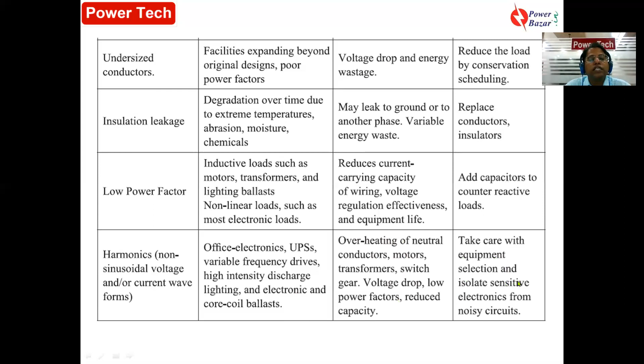Harmonics. What are the reasons? UPS, office electronics, computers, LED, electronic ballast. Now, this results in overheating of neutral conductor, motor, transformer, nuisance tripping, voltage drop, low power factor. These harmonics create a lot of problems. What you have to do? You have to take care of equipment selection, isolate sensitive electronics from noisy circuits, or go for filters.